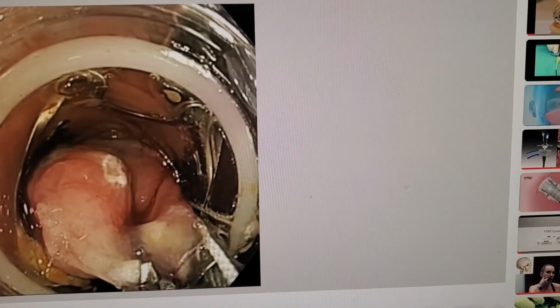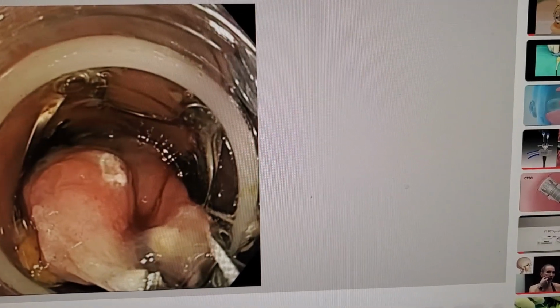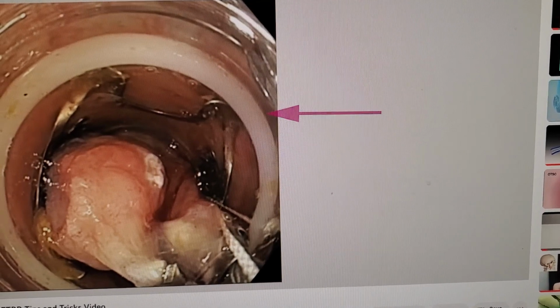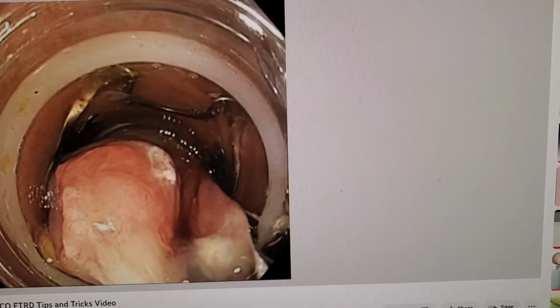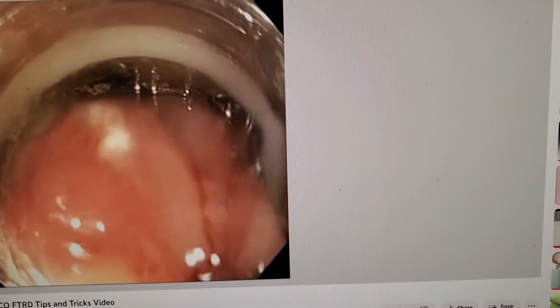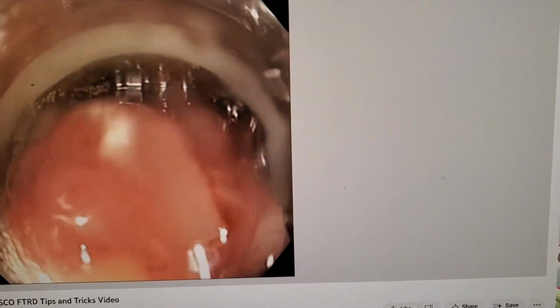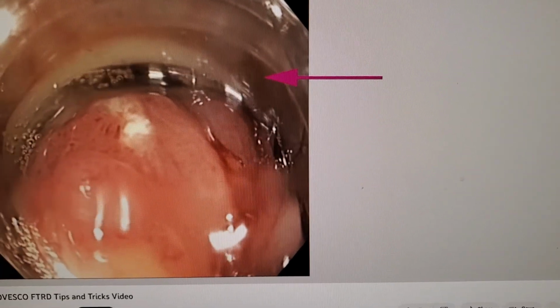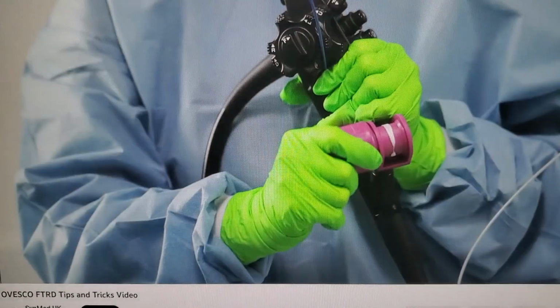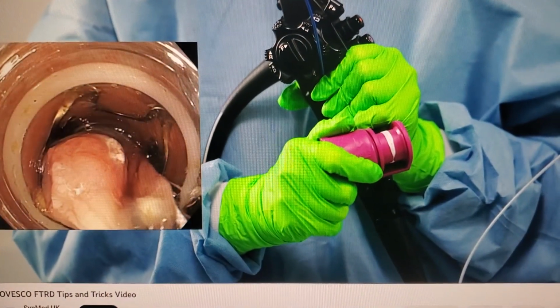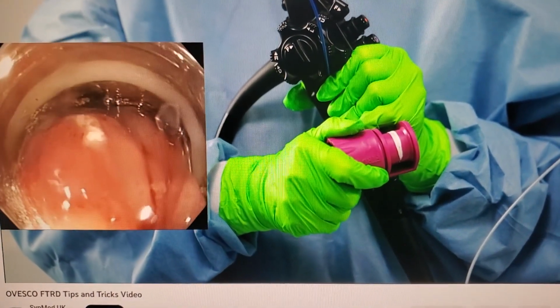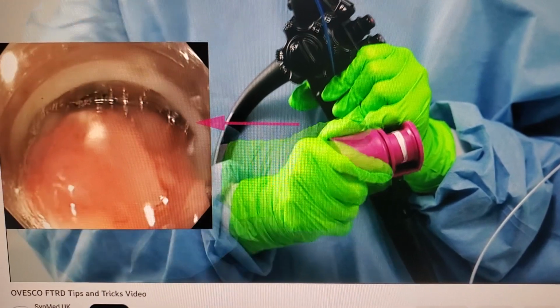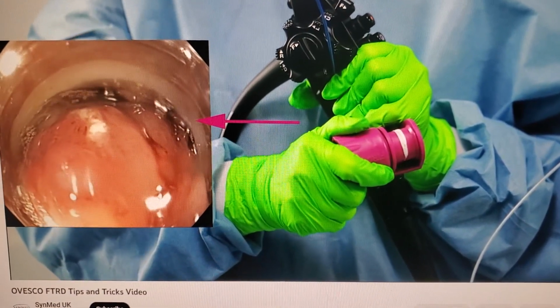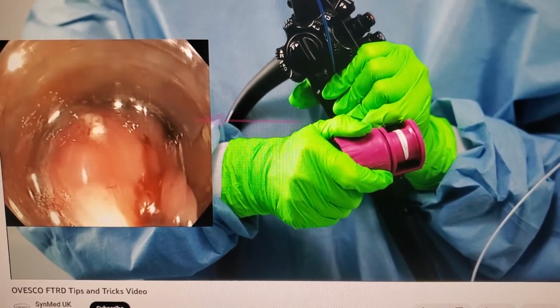Make sure that the clip has been properly applied before resection begins. If the clip has been successfully applied, the white ring will have moved forwards to the edge of the cap. It must remain visible and be observed in the endoscopic image. Only when the white ring has moved fully forwards to the edge of the cap, you can be sure that the clip has been applied. Especially when the endoscope is twisted, for example in the colon, the hand wheel should be turned as far as possible. It may be necessary to reach back and turn it again, so that the force can be transmitted and the clip applied.